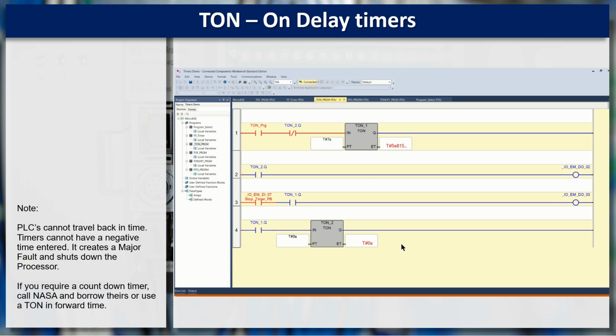So what I have is on my first timer, I'm using the second timer as being not finished as part of my control. So they're free running at the moment because there's not a push button that's starting the whole process. So the first timer is going to count for 7 seconds when it's true. When it's finished, its TON_1.Q will be done, and allows this timer to start timing.